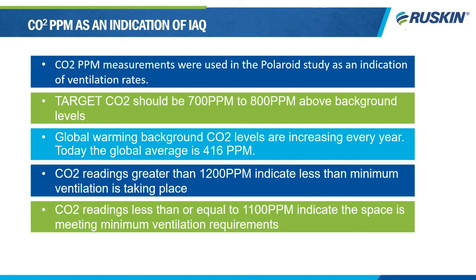A control system should be in place to maintain minimum ventilation rates, and that system should increase and decrease the amount of outside air based on the number of people occupying the space. And normally, we would expect you to close that outside air damper when there's no people in the space and the building's unoccupied.